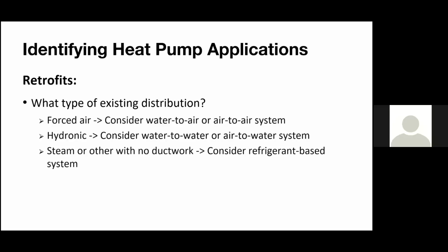So it does depend on how you're planning to distribute your heating and cooling throughout the building, whether you do want the forced air system, whether you do want those radiators, because it might be maybe an older retrofit building with a lot of glass heat. So sometimes, no matter what, you might be looking to have the hot water run near the perimeter of the building, which happens on some jobs. So those are some things to look at. So it is pretty application specific.